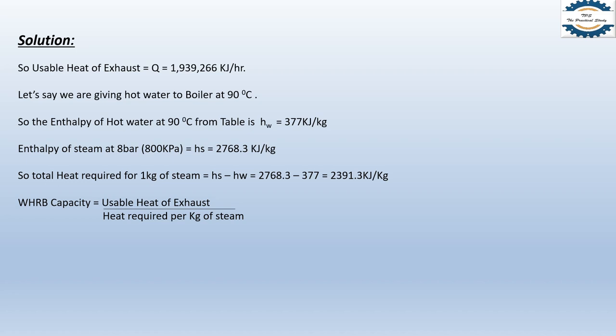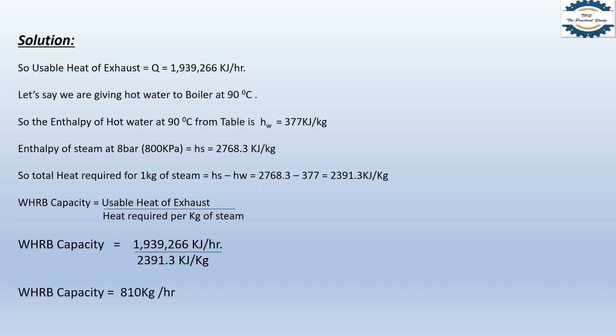The waste heat recovery boiler capacity is found by dividing the usable heat of exhaust by the heat required per kg of steam: 1,939,266 ÷ 2391.3 = 810 kg per hour. In other words, by installing a waste heat recovery boiler on the exhaust of a 1 megawatt gas generator, you will get 810 kg per hour of steam — or 0.810 tonnes per hour of steam.